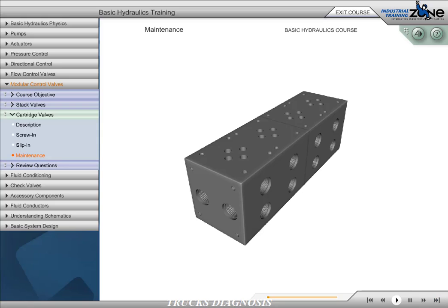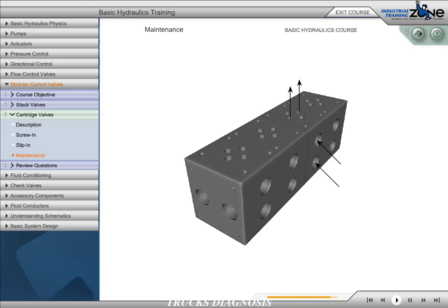Manifold blocks should be thoroughly cleaned before installing cartridge valves. New manifold blocks may have metal chips and other contaminants left in the cavities and passages from the machining process. Prior to assembling, the manifold blocks should be flushed repeatedly. Next, compressed air should be blown through all ports and passages, and each opening wiped clean with a lint-free rag.